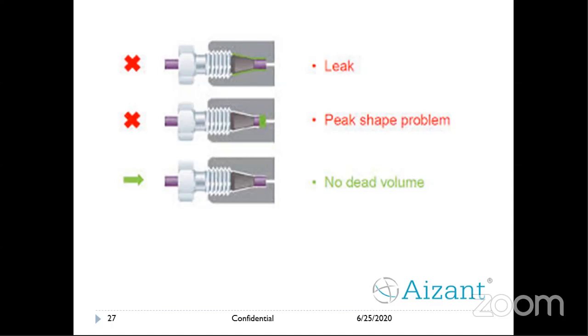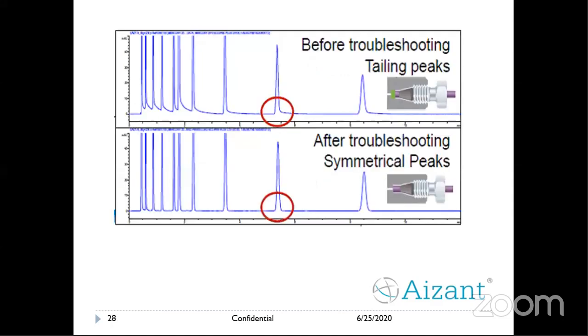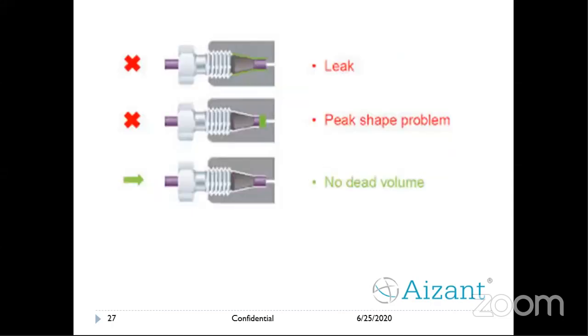In the last one, where there is no dead volume, you can see no solvent is retained in the head of the column. This is the appropriate way to fix the column with appropriate ferrules. I will recommend that in the lab, you will find different ferrules lying there, which will be added to the column. So during fixing of the column, we should take care that there is no leakage, and it should be the appropriate ferrule which we are fixing to the column. If it's not, please take care and replace the ferrule. I think you will save your time and the analysis will be successful.